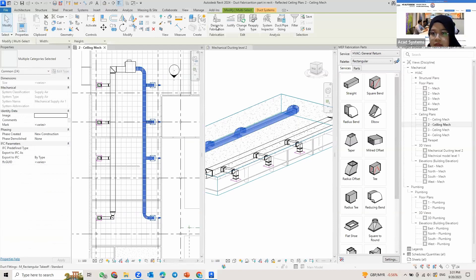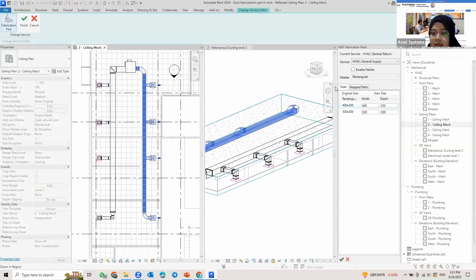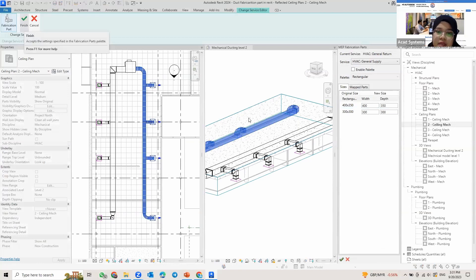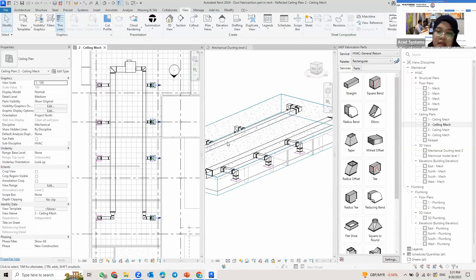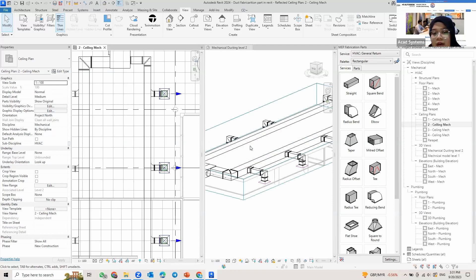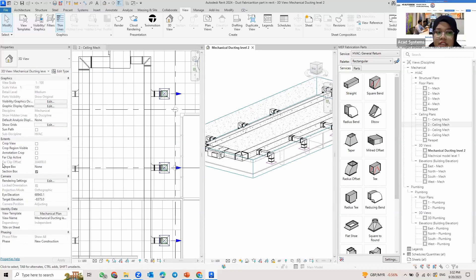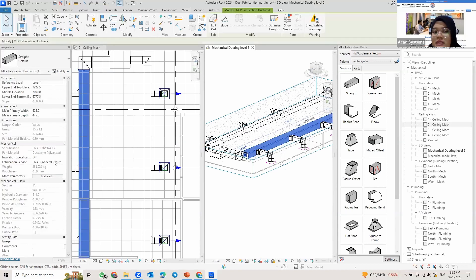The same goes for the supply duct — select everything, go to Filter, select ducts only, and click Design to Fabrication again. Change the services to Supply, confirm it's correct, then click Finish. The supply duct is now also converted to fabrication. What disappears is the color — to check what kind of ducting it is, click on it, go to Properties, and check the fabrication service name.